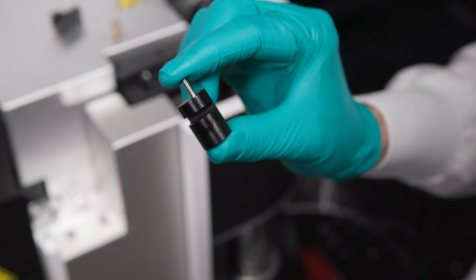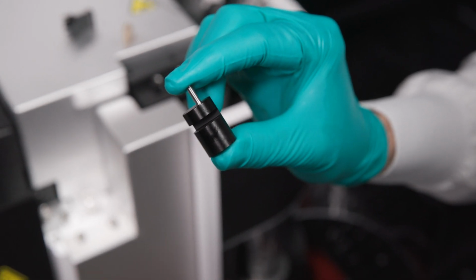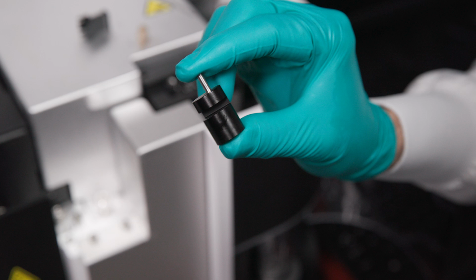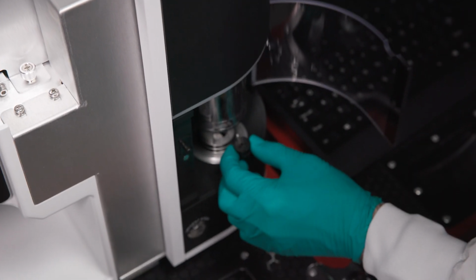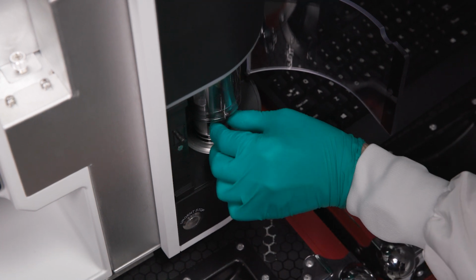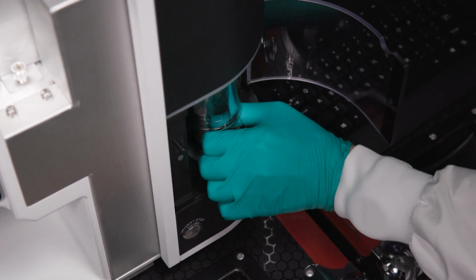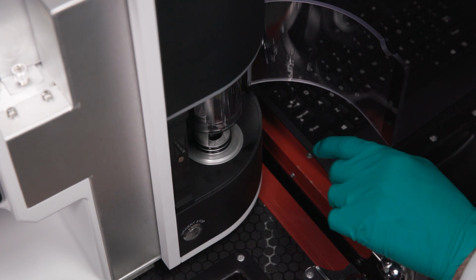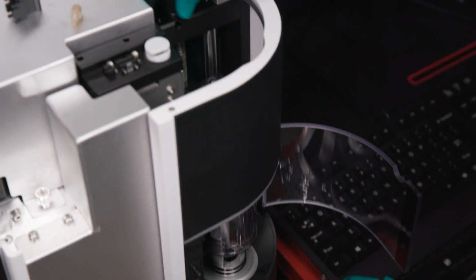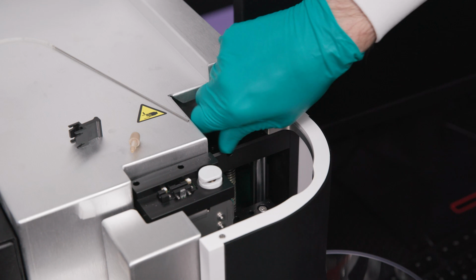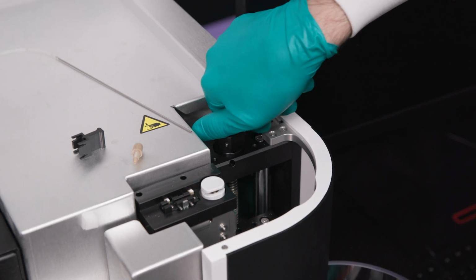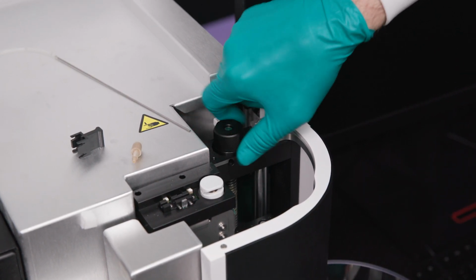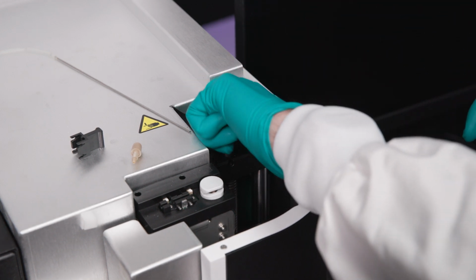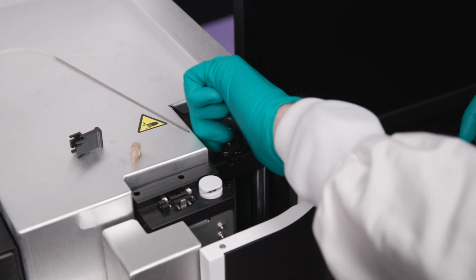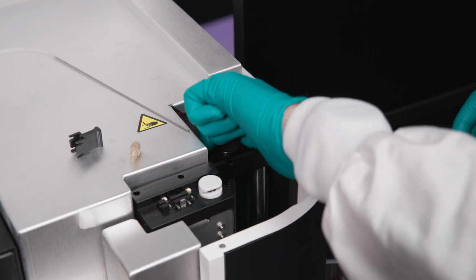Before you begin your sample probe and line replacement, retrieve your sample probe gauge from your fluidics accessory kit. That goes into the sample station in place of the sample holder cup, like so. You'll notice here this nut manually controls the sample station's motion. And we're going to turn it until the sample chamber is at the furthest extent of its downward motion.